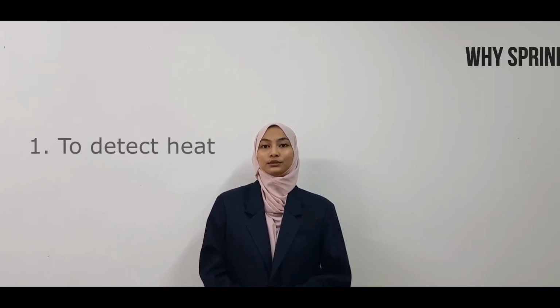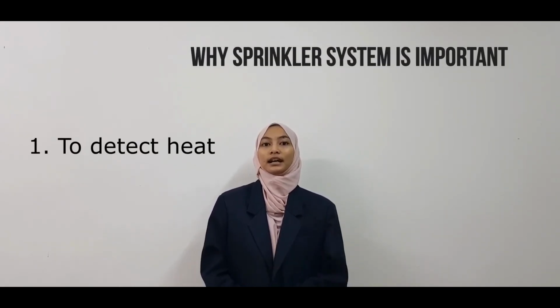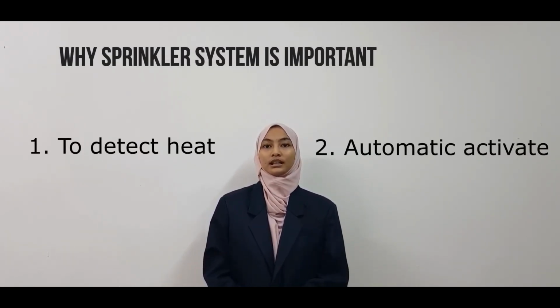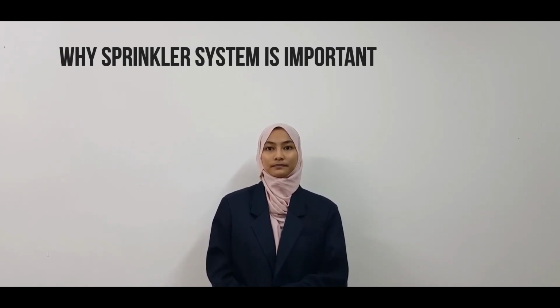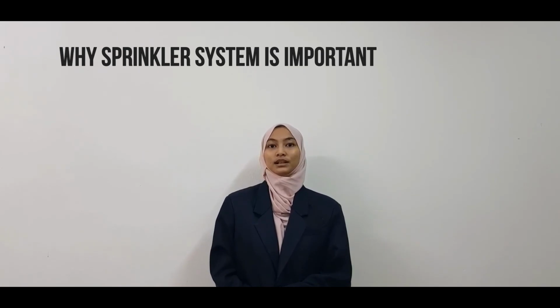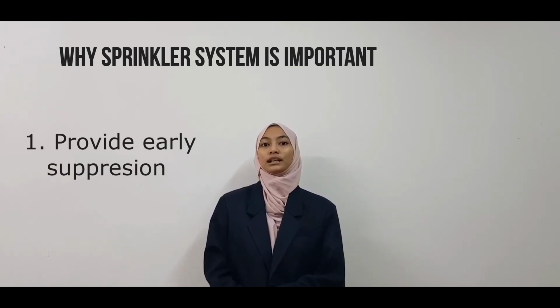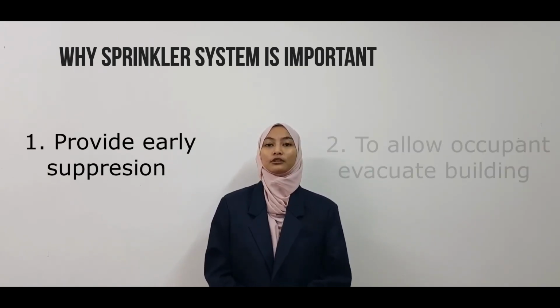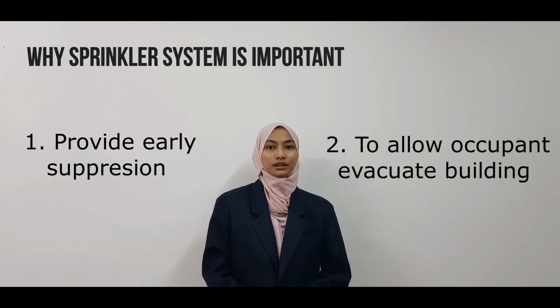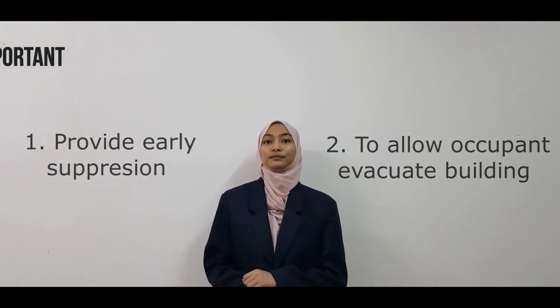Sprinklers are designed to detect heat from a fire and automatically activate, providing a flow of water that is intended to slow or extinguish a fire. Besides that, the sprinkler provides enough early warning to allow building occupants to safely evacuate the building before the fire spread gets worse. And here, I will explain roughly the process of installing the system.